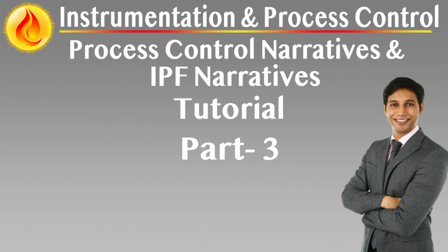Life cycle and operational use. Alarm narratives are developed during the definition phase, with completion of consequence and purpose statements. Operator actions and classification details are finalized during the implementation phase, once the full system design and process operation plans are in place. The completed alarm narratives serve as input to DCS configuration and graphics development, training material for console operators, documentation for alarm audits, HAZOP follow-up, and alarm rationalization reviews, and are referenced during incident investigations or near-miss analyses.